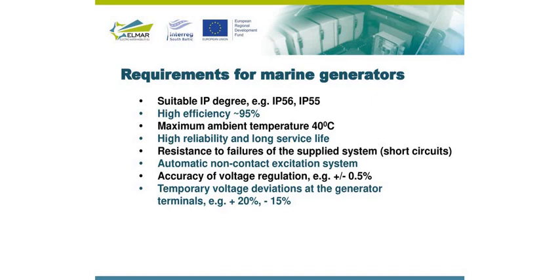Also, accuracy of the voltage regulation is important. It can be plus minus 0.5%, and the generator needs to be proof on temporary voltage deviations, for example, from plus 20% to minus 15%.